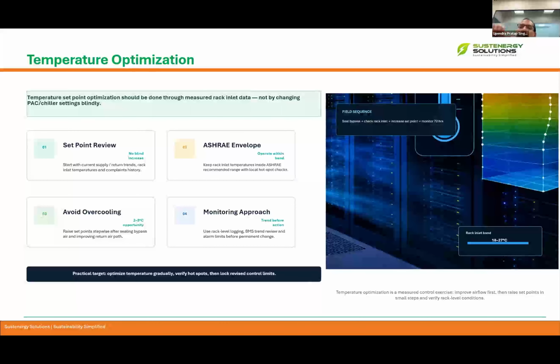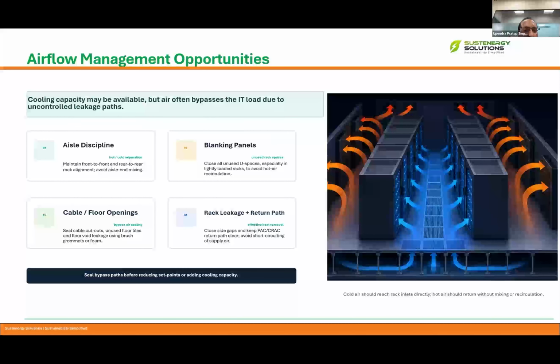Next we will discuss specifically the airflow management opportunity, how we can do airflow management. Cooling capacity may be available, but sometimes air bypasses the IT load due to uncontrolled leakage paths. Some of the problems which affect airflow management: one is aisle discipline. We need to maintain proper hot aisle and cold aisle separation so that the hot and cold air don't mix. We need to maintain front-to-front and rear-to-rear rack alignment and avoid aisle mixing.